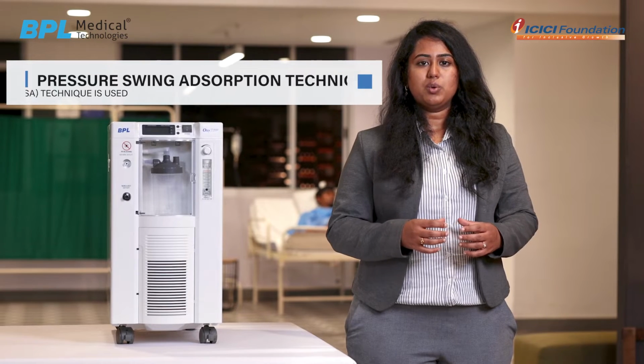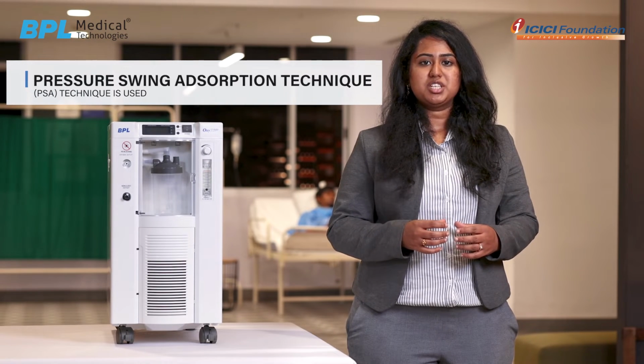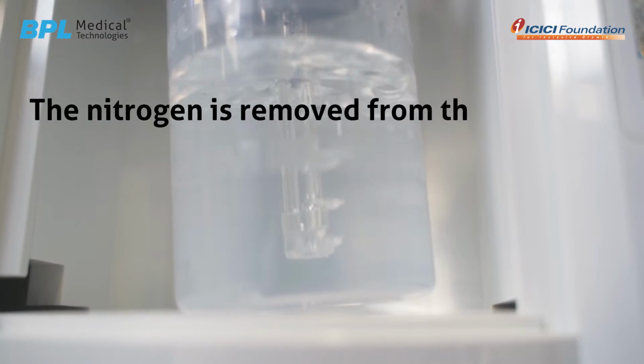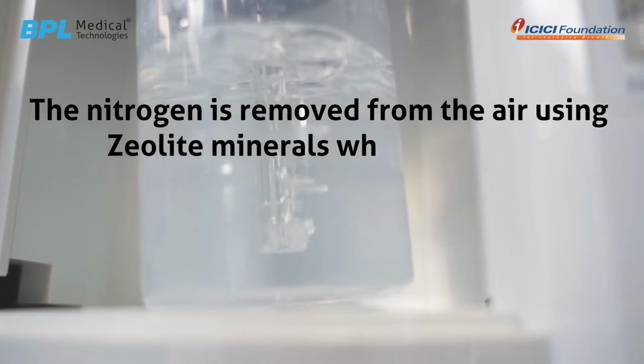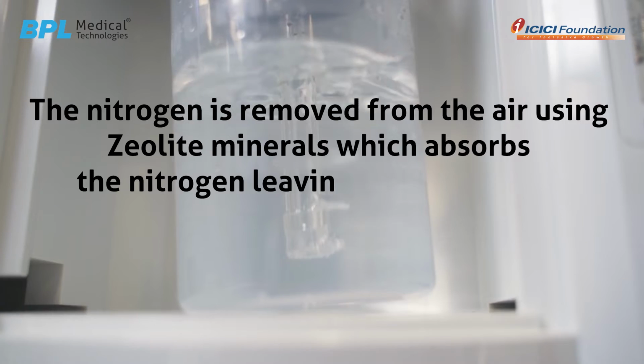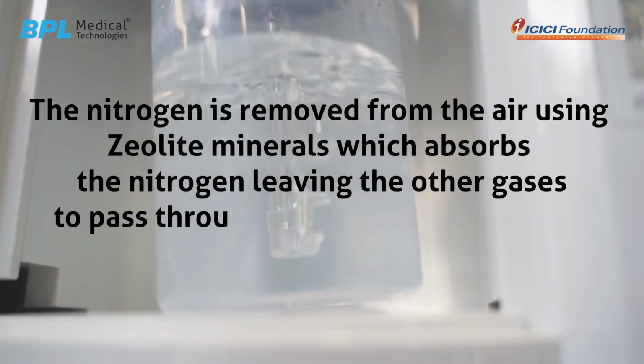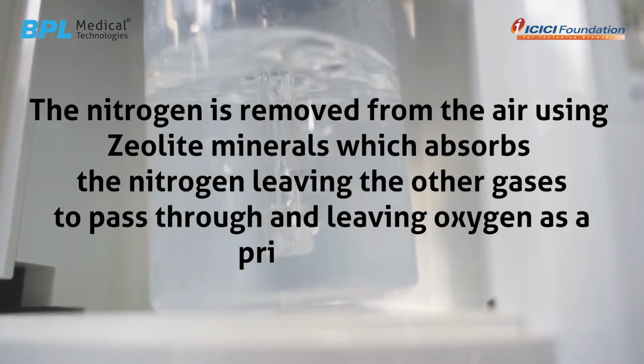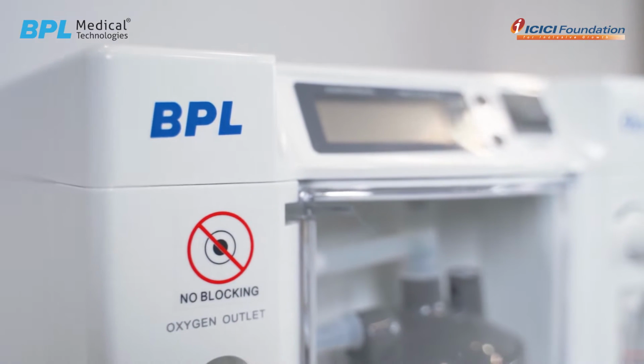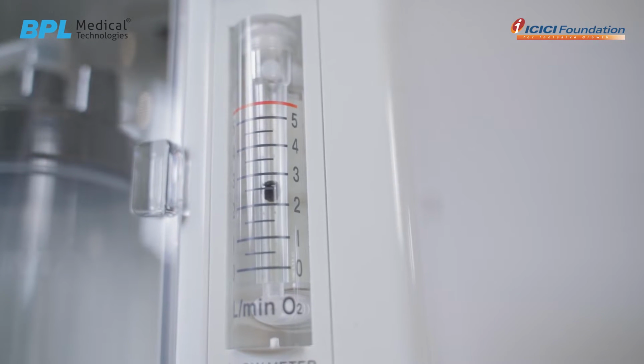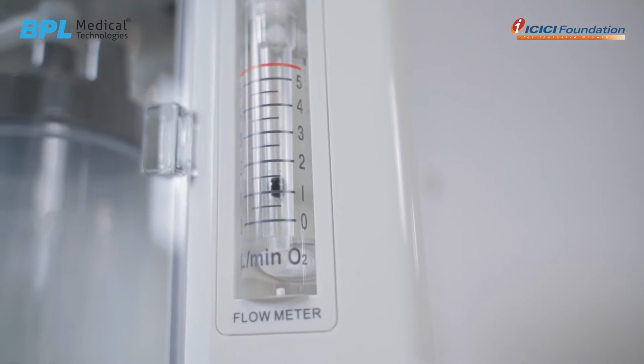Oxygen concentrator works on pressure swing adsorption technique, that is PSA technique, where the nitrogen is removed from the air using zeolite minerals which adsorb the nitrogen, leaving the other gases to pass through and leaving oxygen as a primary gas. BPL oxygen concentrators have inbuilt sensors that monitor oxygen levels, which is shown through LED lights.